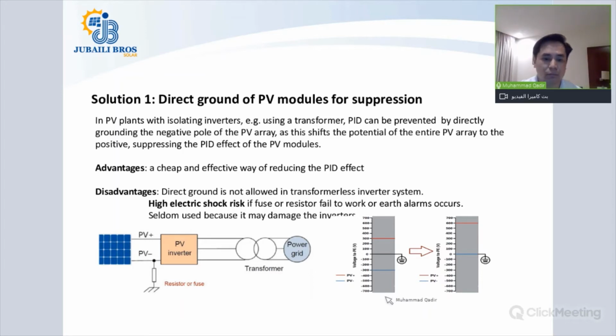Just to give you a more detailed overview, here is this graph on the right side. You can see that normally your PV strings have a negative and positive potential. After you have connected the negative side of your PV module string to earth, both the negative side and the earth will be at the same potential. Thus, the whole PV module string potential will be shifted to the positive side, and this will also suppress the PID effect.